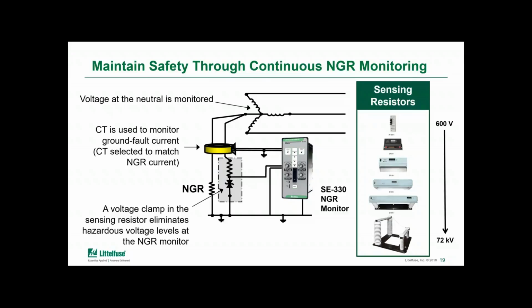Yes. So the purpose of this, it's a back-to-back Zener diode, and really that's a voltage clamp, because that is the connection point for an NGR monitor to the neutral. There is voltage on the neutral during a ground fault, and we want to make sure that that voltage does not pass through to the relay. So the resistance on the top half is very large to drop virtually all of the voltage when there is a ground fault, but that voltage clamp on the bottom will ensure that even if for some reason there is unsafe voltage present on that center point, that voltage becomes clamped to ground. So it provides protection for the control circuit that's running to the relay.